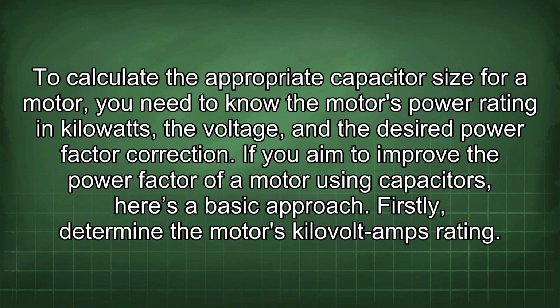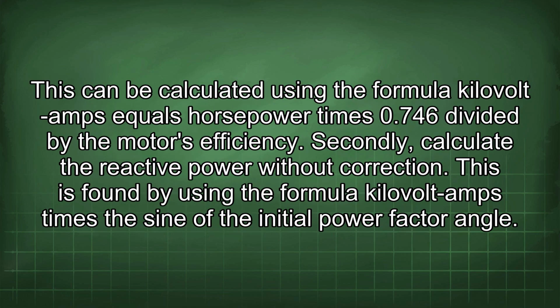To calculate the appropriate capacitor size for a motor, you need to know the motor's power rating in kilowatts, the voltage, and the desired power factor correction. If you aim to improve the power factor of a motor using capacitors, here's a basic approach. Firstly, determine the motor's kilovolt amps rating. This can be calculated using the formula kilovolt amps equals horsepower times 0.746 divided by the motor's efficiency.